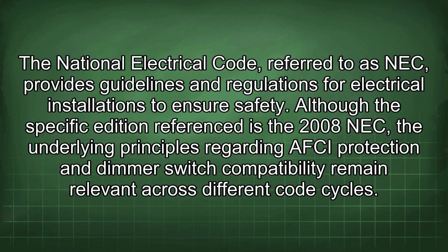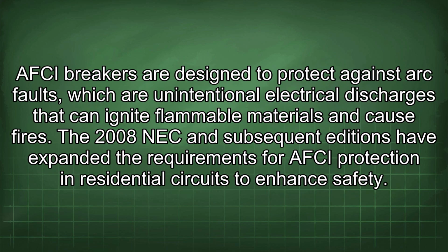The National Electrical Code, referred to as NEC, provides guidelines and regulations for electrical installations to ensure safety. Although the specific edition referenced is the 2008 NEC, the underlying principles regarding AFCI protection and dimmer switch compatibility remain relevant across different code cycles. AFCI breakers are designed to protect against arc faults, which are unintentional electrical discharges that can ignite flammable materials and cause fires. The 2008 NEC and subsequent editions have expanded the requirements for AFCI protection in residential circuits to enhance safety.